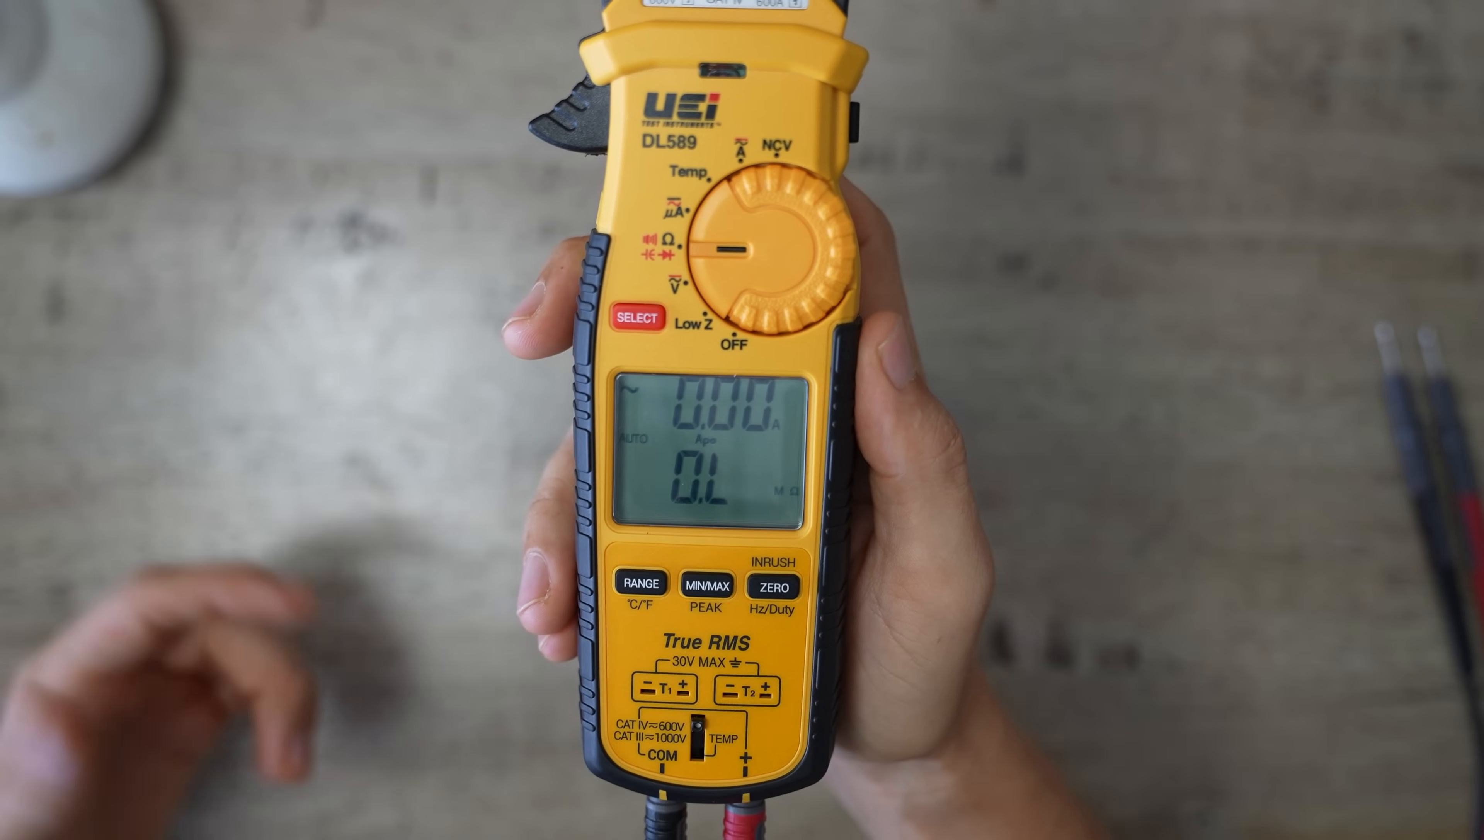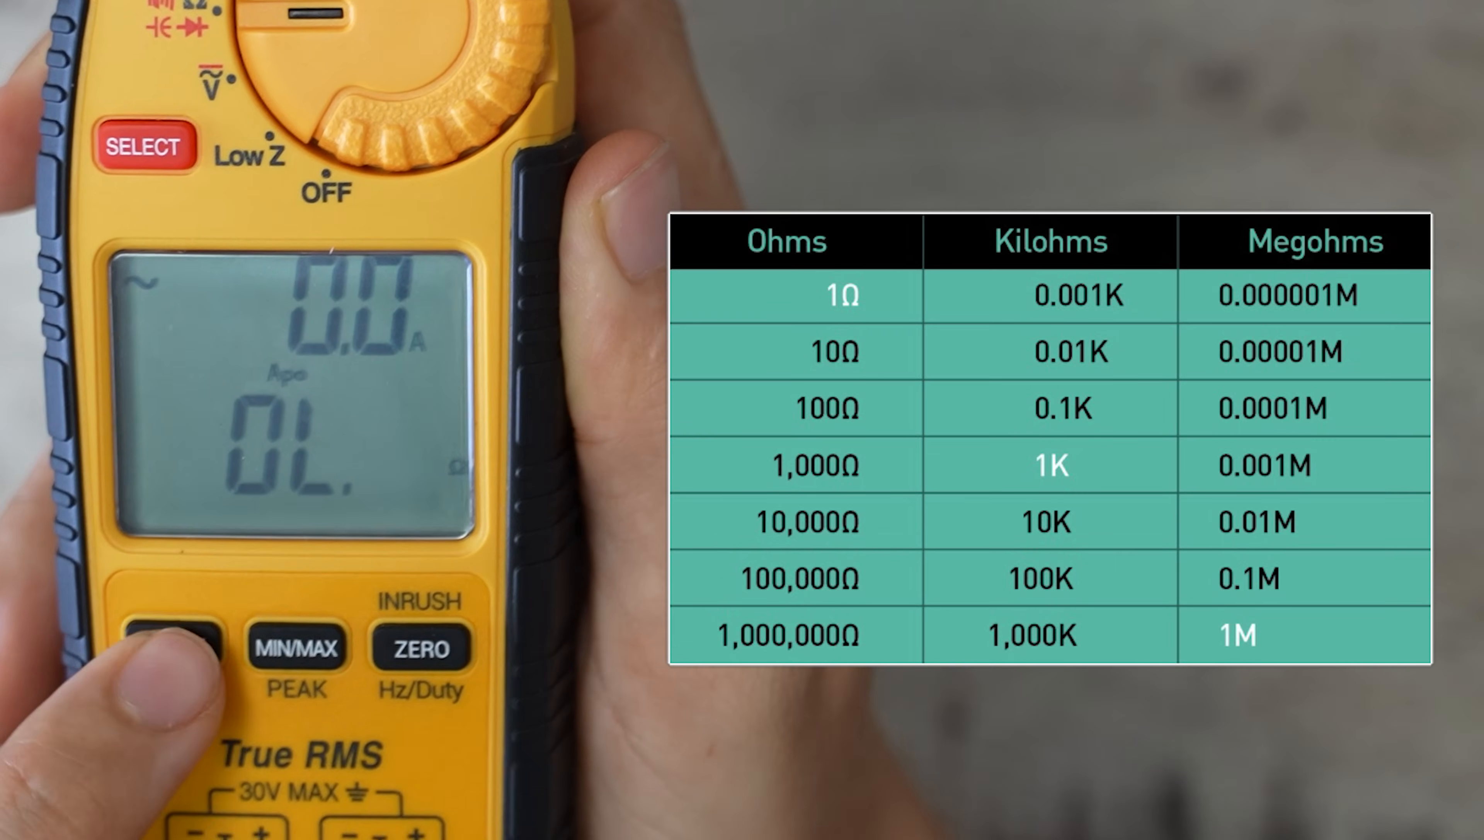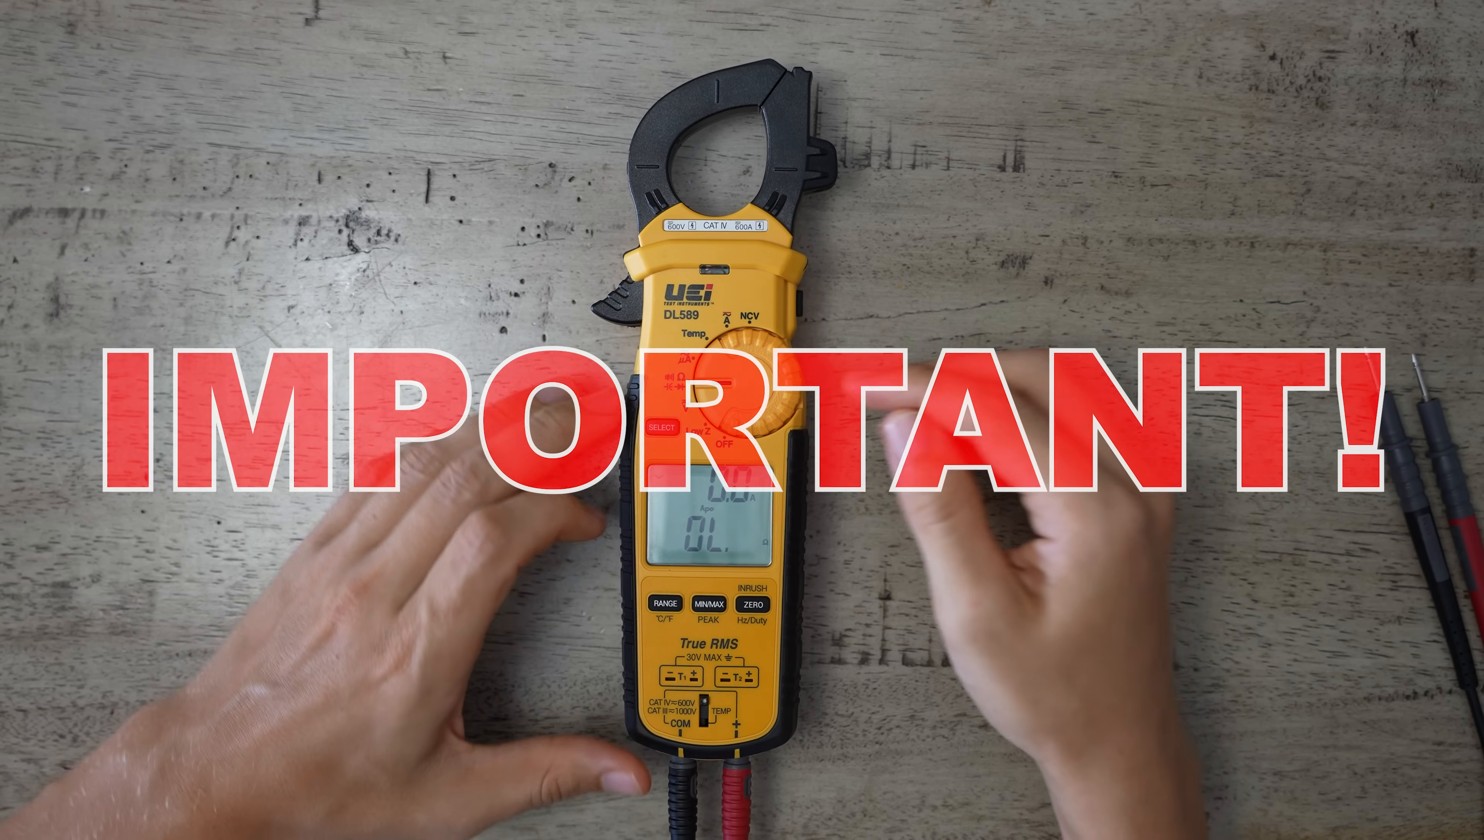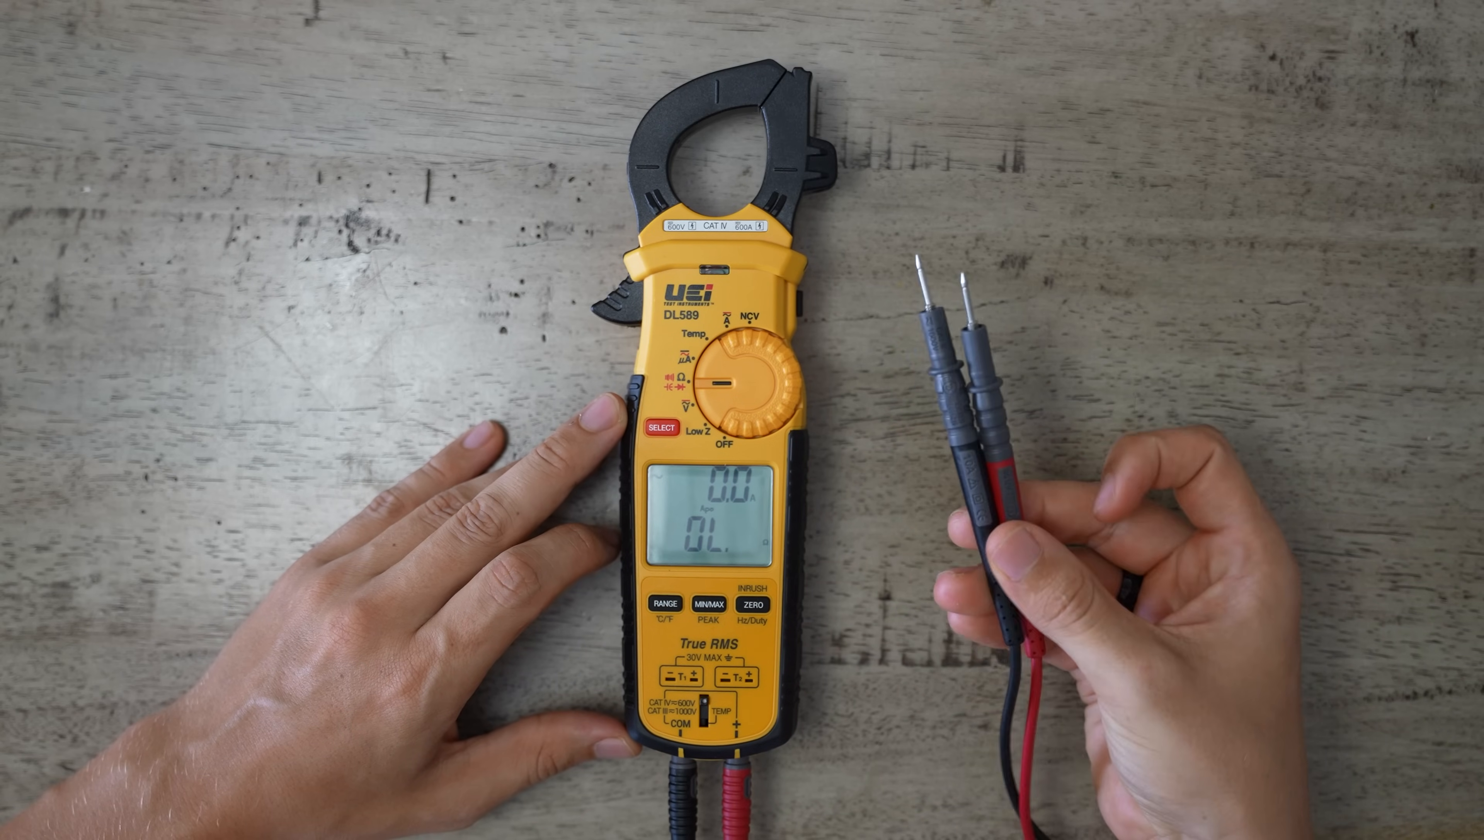Auto-ranging meters will automatically select the proper range for you, but it does allow you to manually switch the range if you want to do so. All I have to do is just press this range button, and it'll switch from ohms to kilo-ohms, and then higher, higher, mega-ohms, even higher, and back to ohms. Also, one very important thing to remember when you have your meter set to this resistance setting right here, is that the power has to be off to whatever you're checking. Power off, and usually the wires have to be disconnected before you check resistance on anything.